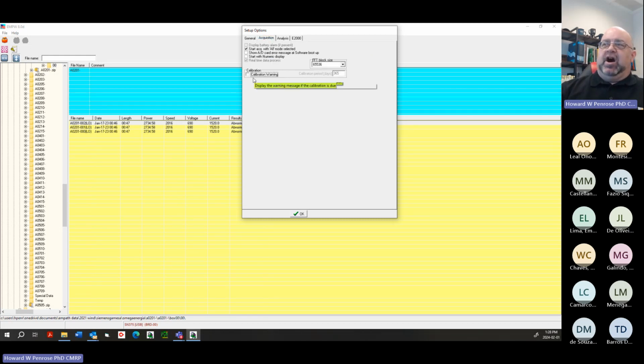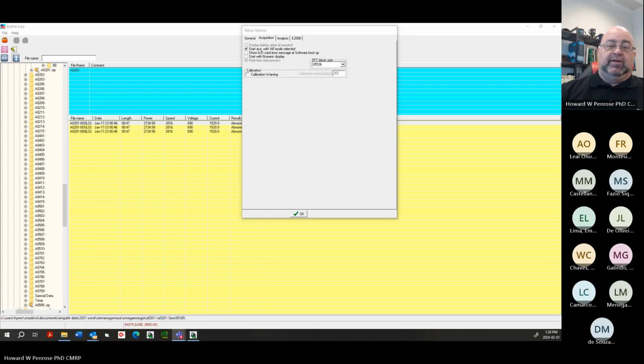Under acquisition, uncheck calibration warning. That's really annoying. The other thing you want is, in some versions of the software, for whatever reason, the programmer left it at 1024. You want the FFT block to be 65,536. The reason for that is to get the resolution we want, especially when the machine is extremely lightly loaded, or you're trying to discern whether you've got a blade pass frequency going on for the blades or a problem going on with the wiring. Those are going to show up almost in the same region.